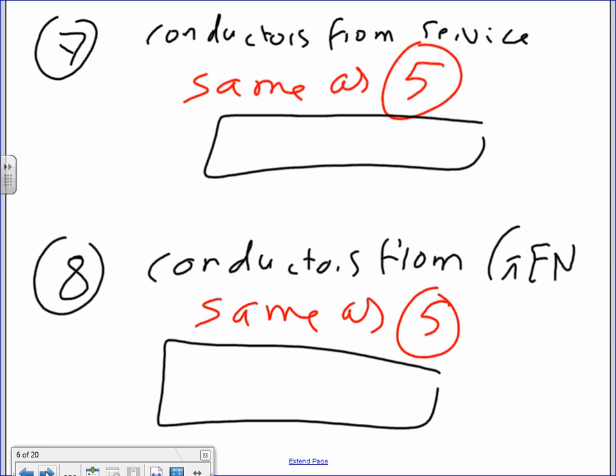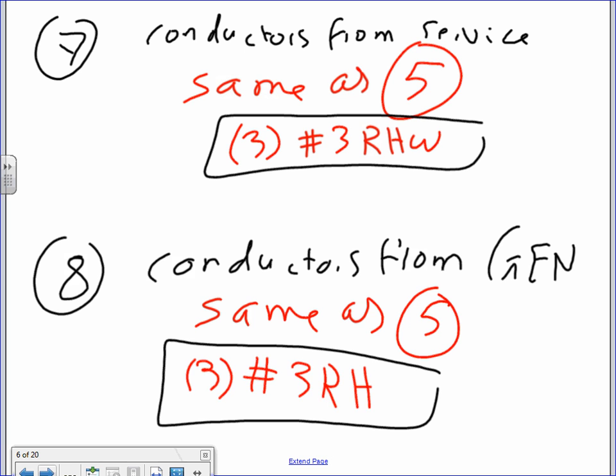Number 7, conductor from service, same as number 5. Can you guess that? No, the conductor from the service, it says same as number 5. So 3 conductors, you go to step number 5, same, 3 number 3 RHW, done. Conductor from the generator, same as number 5. So that will be the same conductor. 3 number 3 RHW. Same conductor. Can you guys see that? No gimmicks, nothing at all. Matt, makes sense?